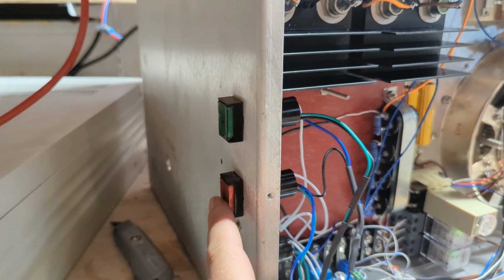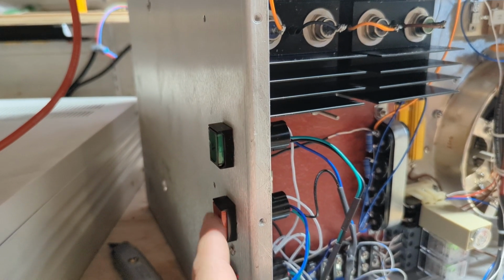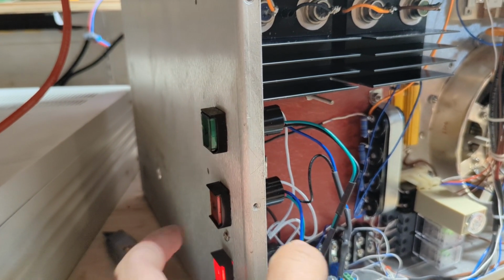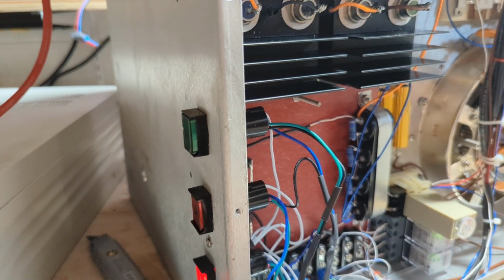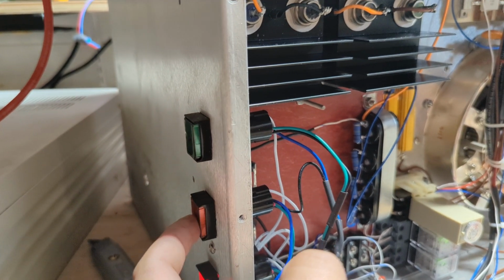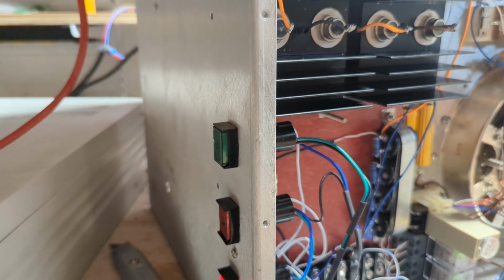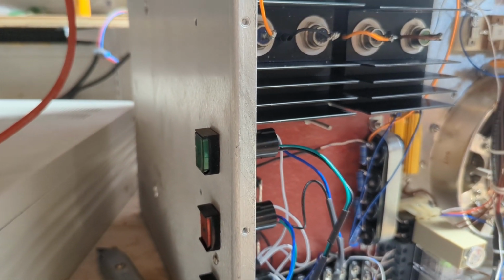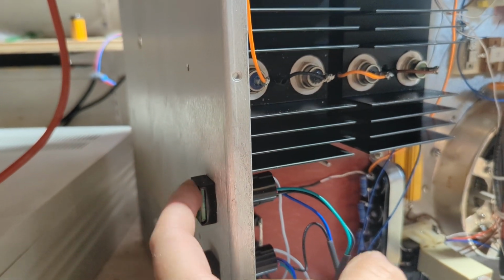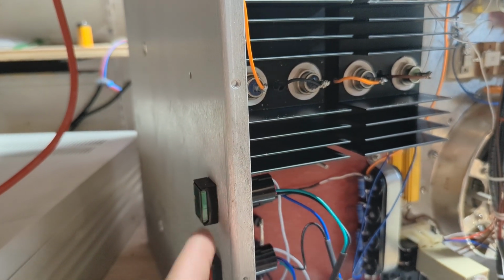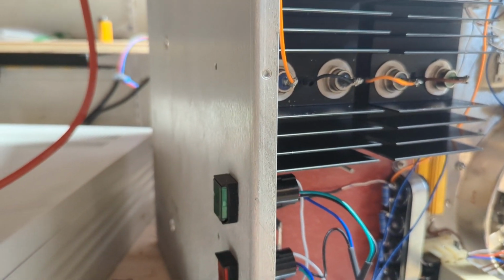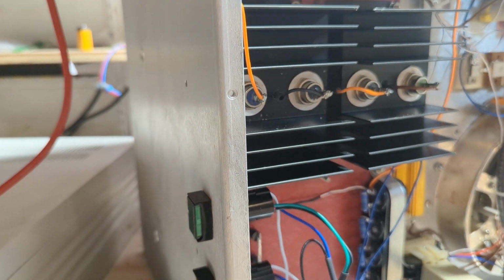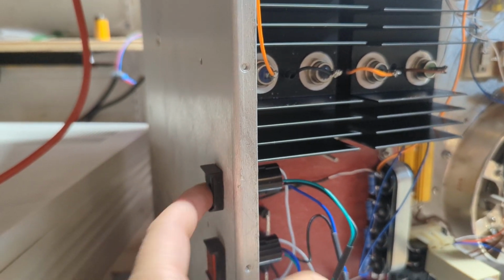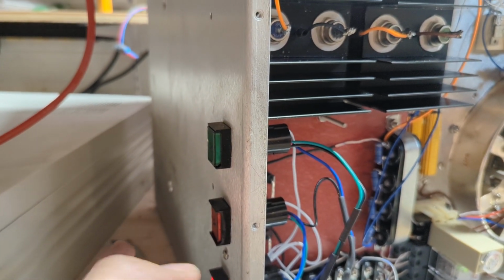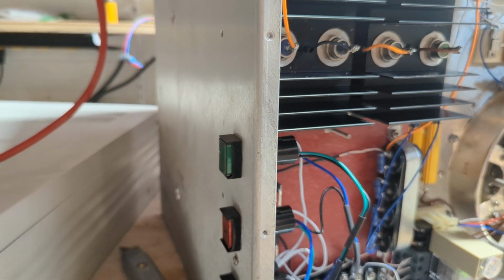Next is the high voltage switch, which asks the power supply to provide high voltage. So again, you're asking for the high voltage, but right now there's no high voltage, so it's never going to turn on, and it's never going to let you turn the standby operate switch, which would engage the screen. So you can't engage the screen since there's no high voltage - you're asking for it, and there isn't any.